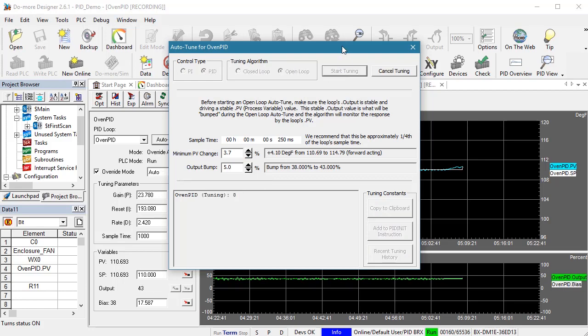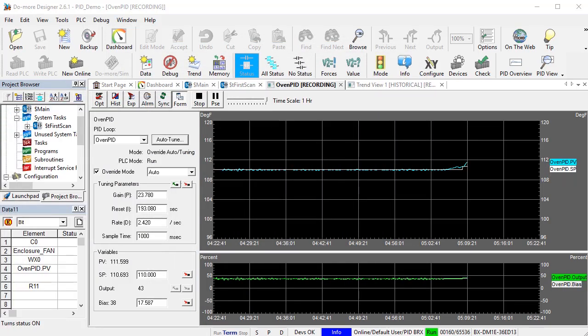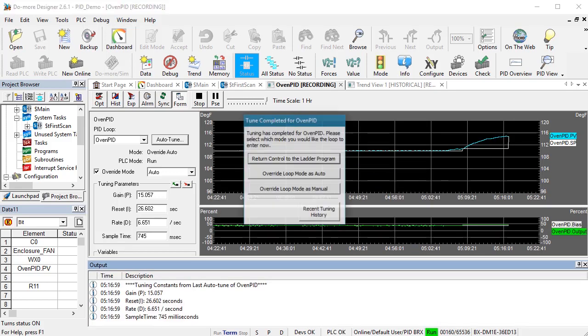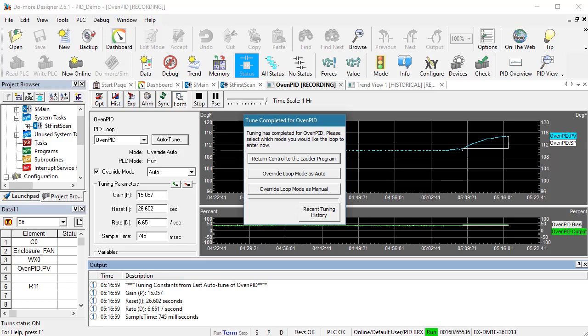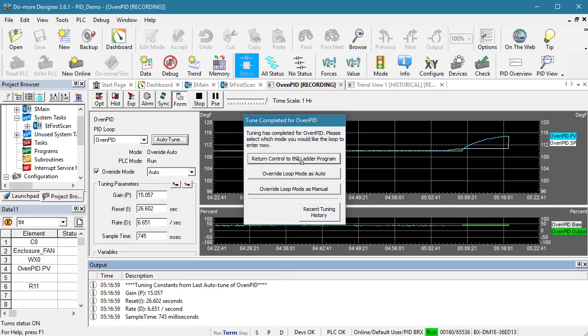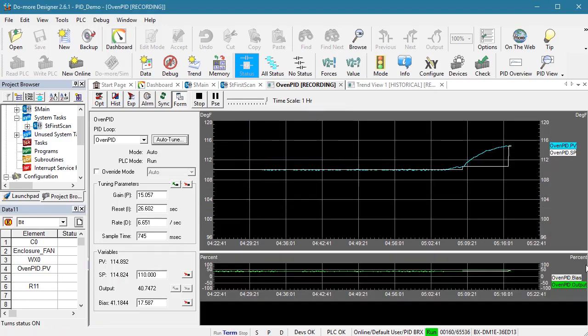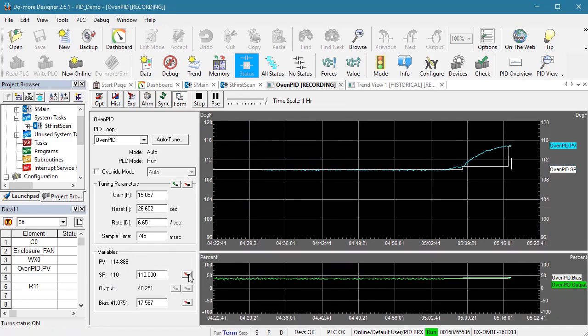This is going to take several minutes so I will fast forward. Great. We see Auto-Tune move the setpoint to mark the starting point and we see the process variable rose on that curve that we expect to see until it got to about 4 degrees. Auto-Tune then moved the setpoint to that level to mark where we stopped. And I will return to the ladder program control and reset the setpoint to 110 degrees.